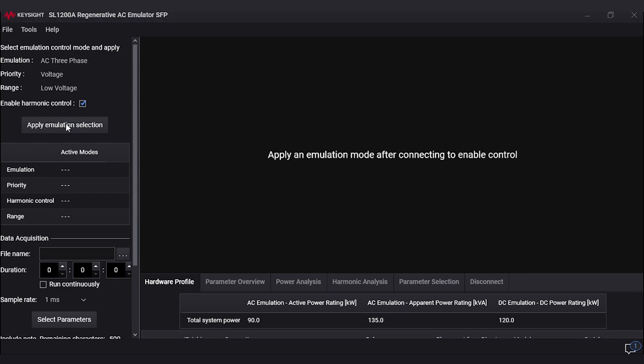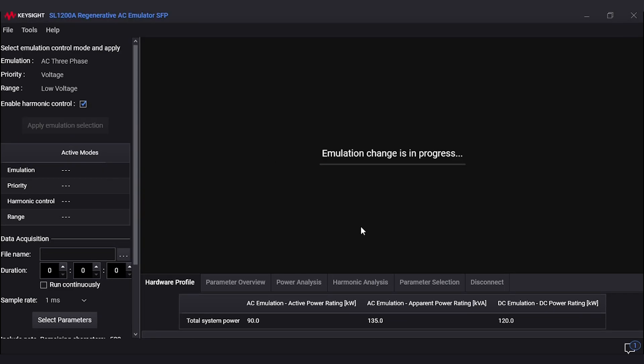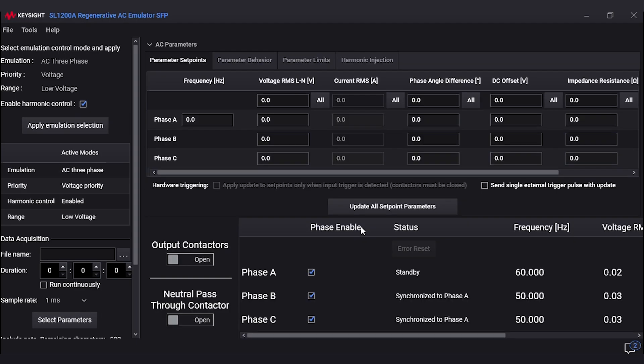The first thing you should look at is your frequency to make sure it matches the input that your load takes. Ours is 60 hertz, so there is no change needed.